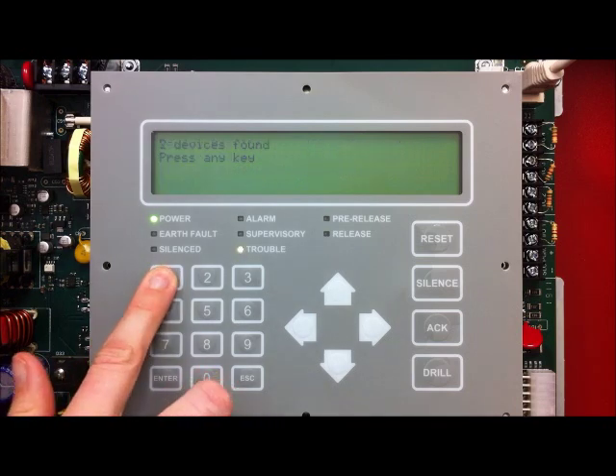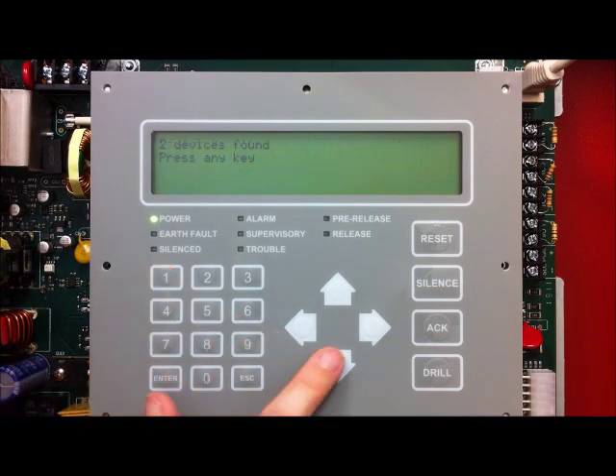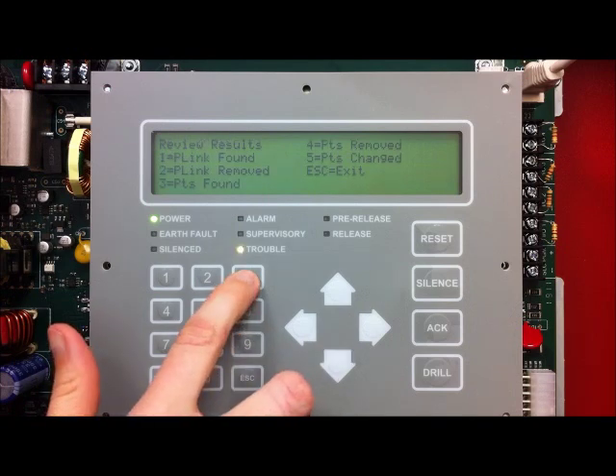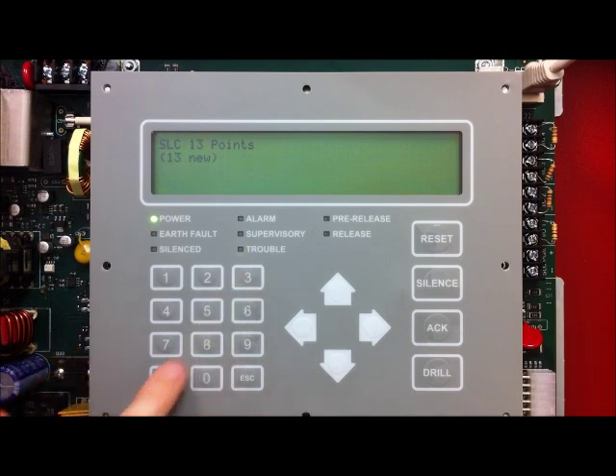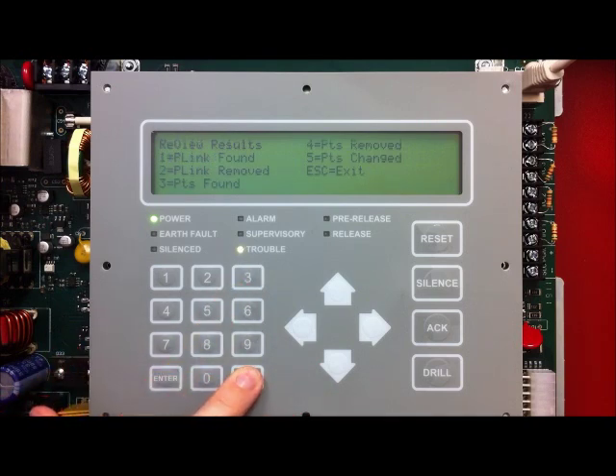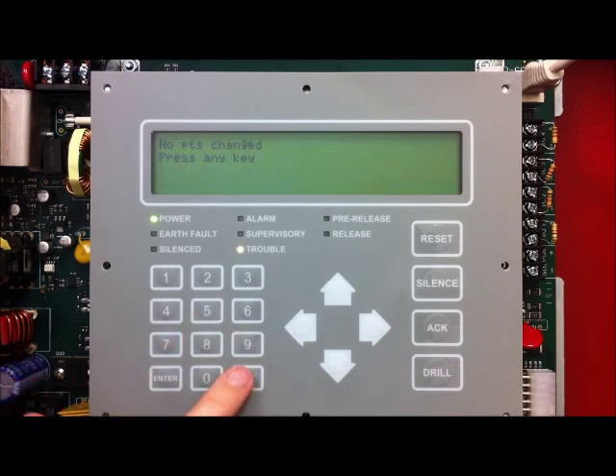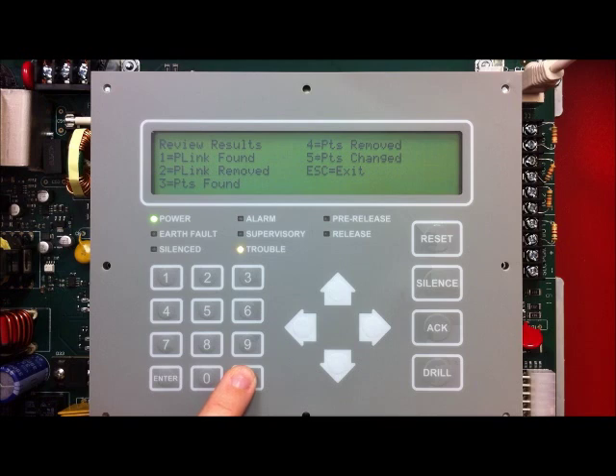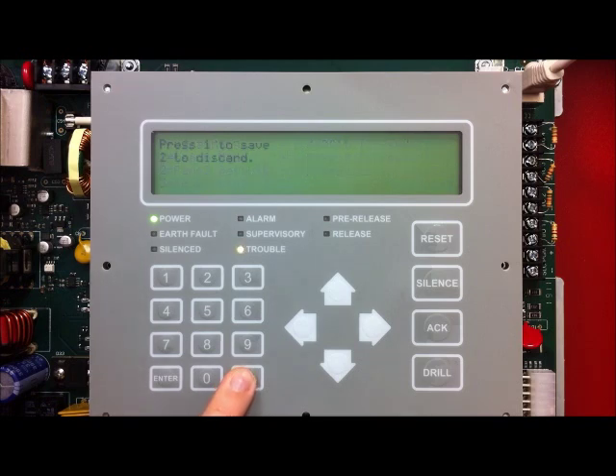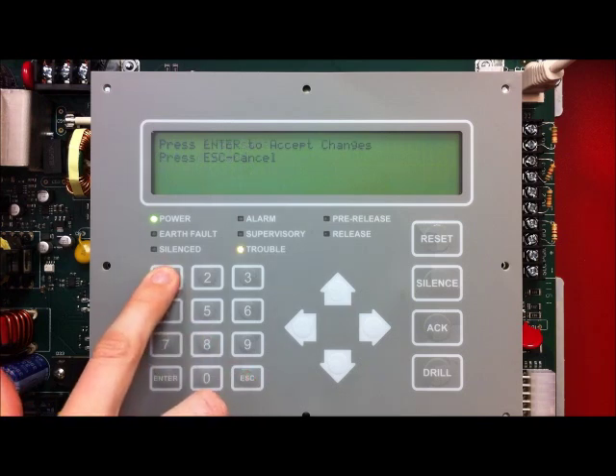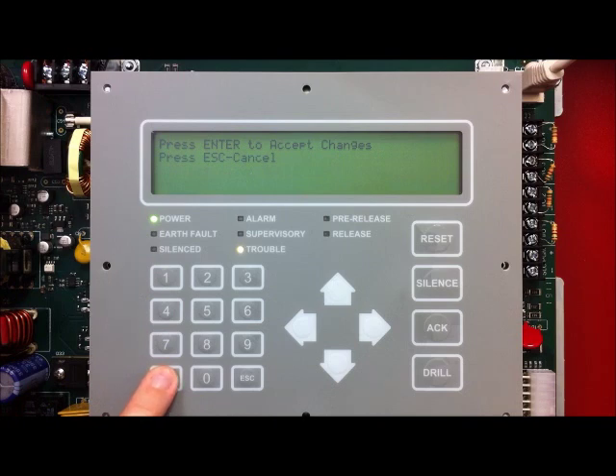To review results, select which option you would like to see. I will select 1, PLINK found. It found two devices, and I can hit the down arrow to see that it was an LCD and a power supply. Going through each option, it will tell you how many points were found, points removed, or points changed. Once you are done reviewing, press the ESC key to get back to the programming menu. From the programming menu, press ESC again. It will then ask you to press 1 to save or 2 to discard. I am going to save my changes and press ENTER to accept, and the system will restart.